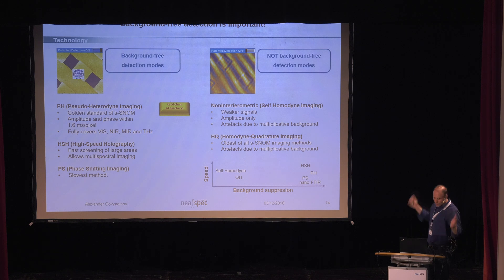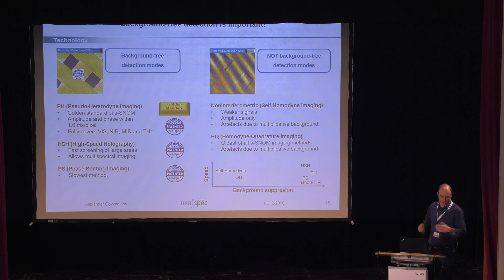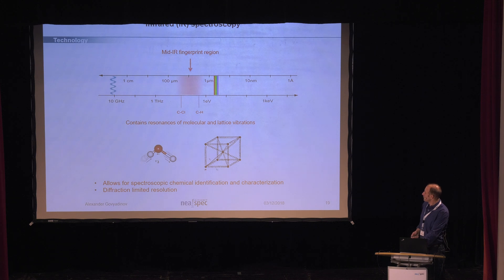So, this is kind of a short summary of some detection modes. These are detection modes which provide the multiplicative background suppression. Some of you might have heard of pseudoheterodyne. It's probably the golden standard of SNOM nowadays. Then there is also two more methods: high-speed holography and phase shifting. The good thing for us, at least, that all three of them are patented and there's proprietary modes for neaspec technology. And this is just a reminder what happens if you don't suppress the multiplicative background and you don't use the proper detection modes.